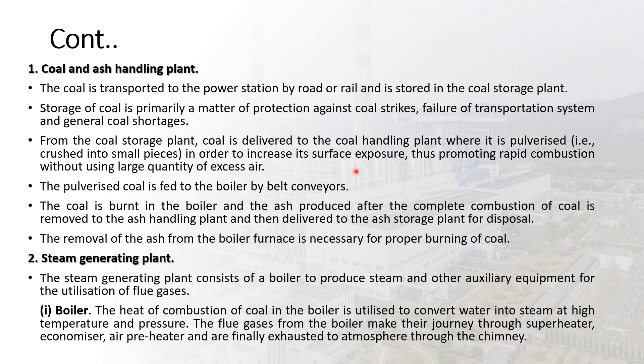The coal is pulverized to increase its surface exposure, promoting rapid combustion without using large quantities of excess air. The pulverized coal is fed to the boiler by belt conveyors. The coal is burned in the boiler and the ash produced after complete combustion is removed to the ash handling plant and then delivered to the ash storage plant for disposal.